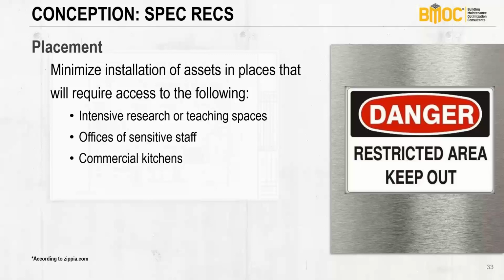Commercial kitchens are always very busy, so it's difficult to coordinate maintenance in there. When you can, have centralized refrigeration systems in a mechanical room that's out of the way, maybe accessed from outside rather than through the kitchen space. Also, especially avoid above-ceiling equipment - sometimes you see dishwasher fans in line, located above the ceiling right in the dishwasher space.